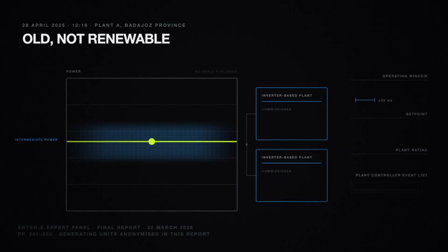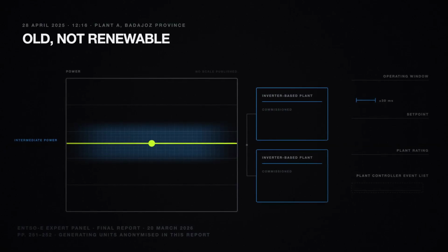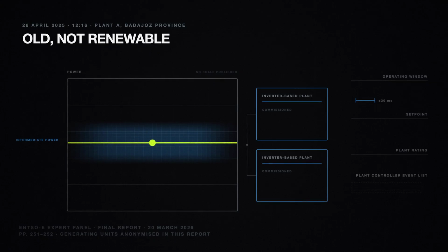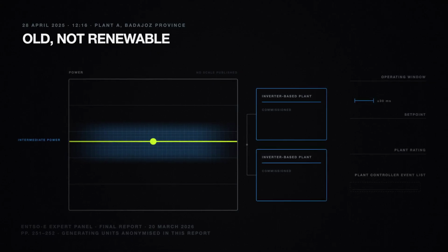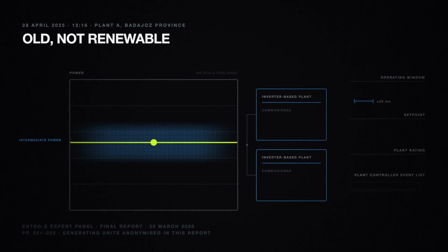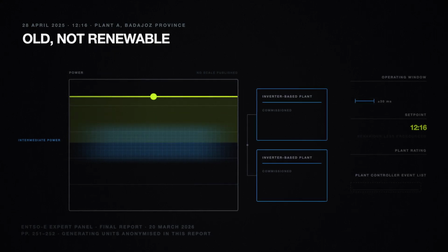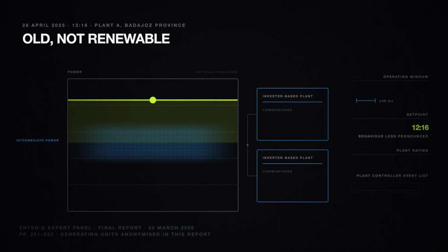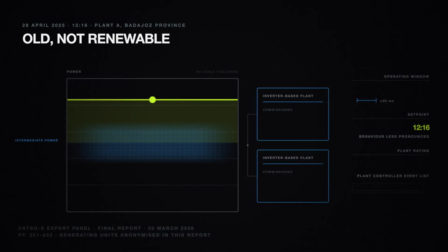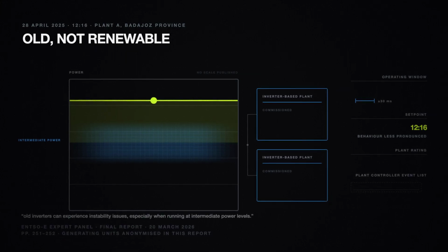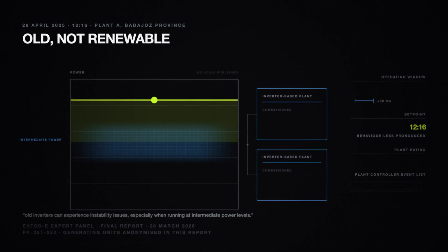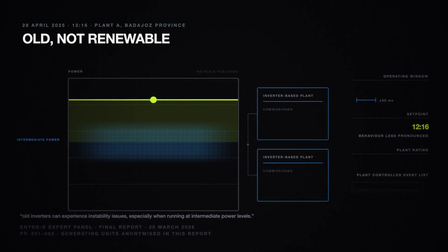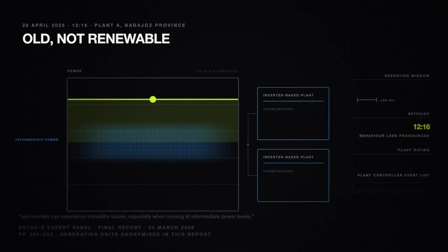16 minutes past 12. The plant increased its power set point, and its oscillatory behavior became less pronounced. That is the report's sentence, and it runs the opposite way to the shape of the story. The machine got steadier by being turned up. The mechanism the panel gives is age and operating point. Old inverters can experience instability issues, especially when running at intermediate power levels.